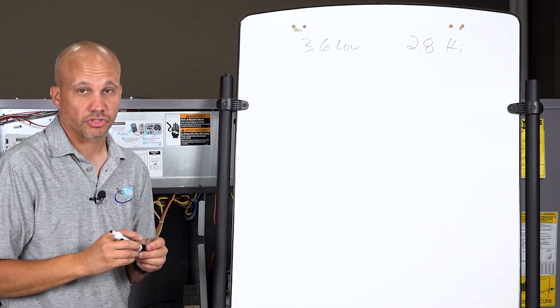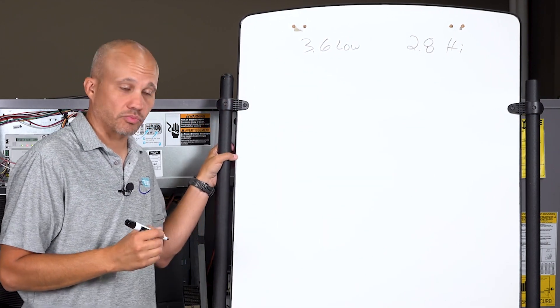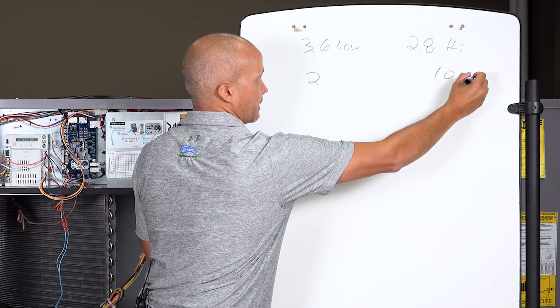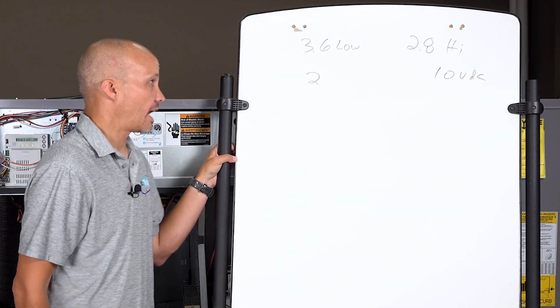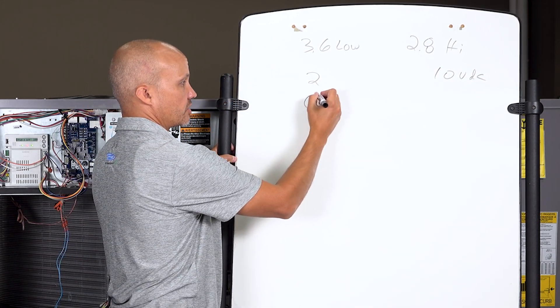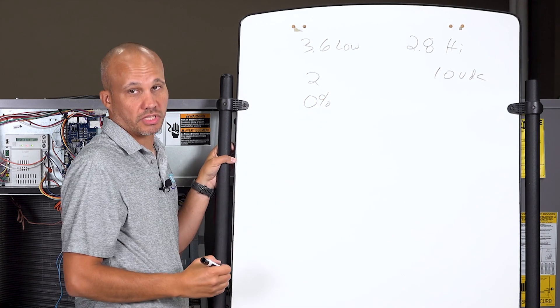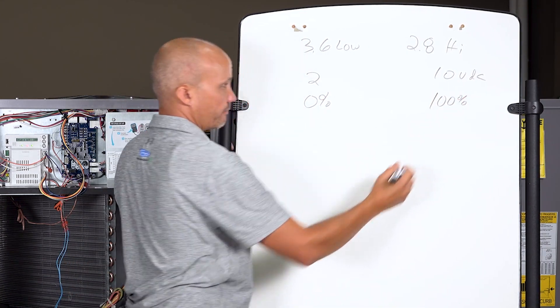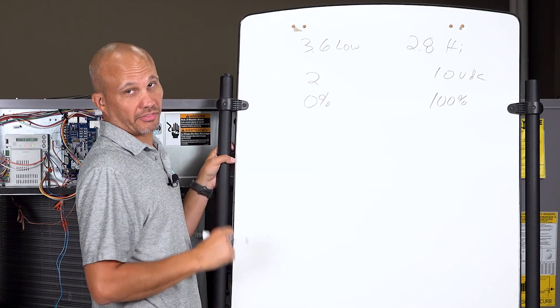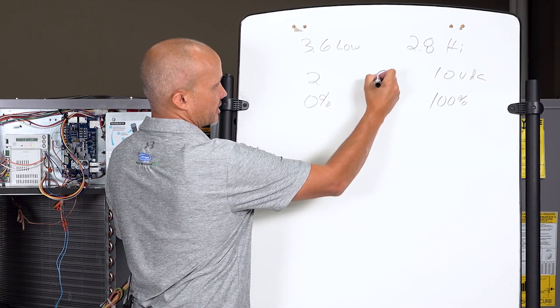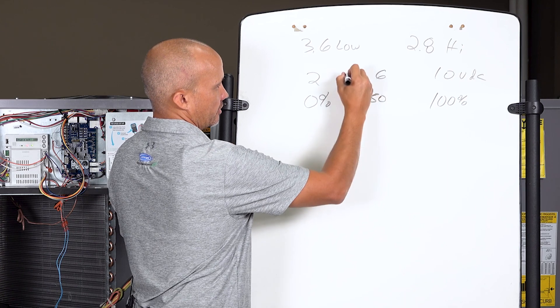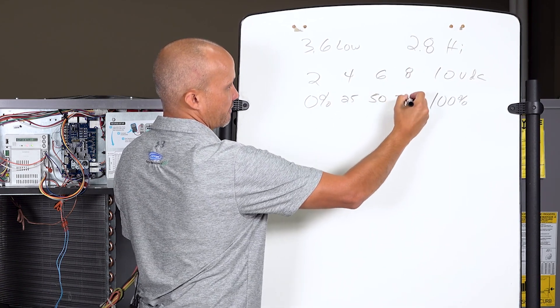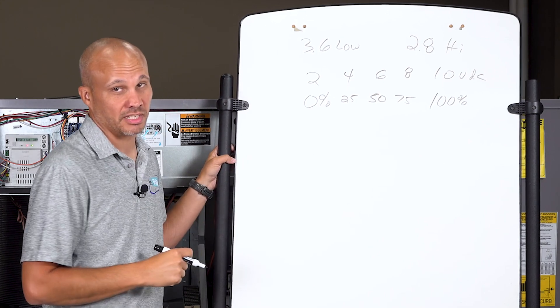For starters, the way this works is these actuators go from 2 to 10 volts DC. That means 2 volts means zero percent - close the damper. 10 volts means 100% - open the damper wide open. The middle of the range is not 5, it's 6. That's 50 percent. 4 volts would be 25 percent, 8 volts would be 75 percent.